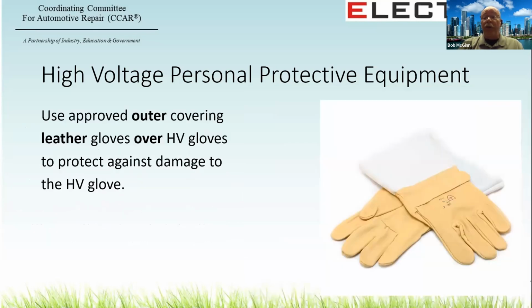Make sure your students are using the outers. There are outer leathers that are always accompanying your high voltage. They should come as a kit with the rubber inners that are high voltage and the outer leather that protect them. The outers need to be inspected for damage or contamination, especially contamination. And why? Because at 400 to 600 volts, contaminants may be conductive, whereas at 12 volts, no one would notice.